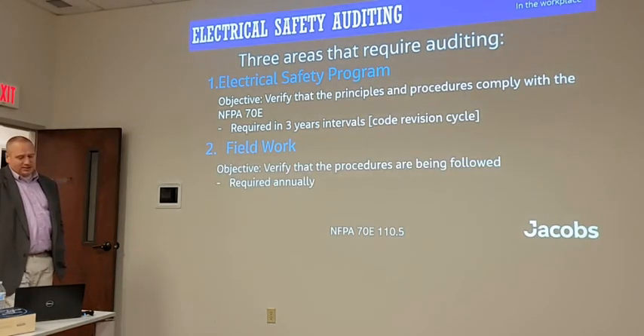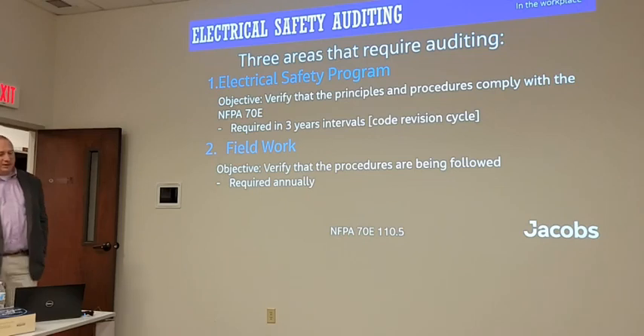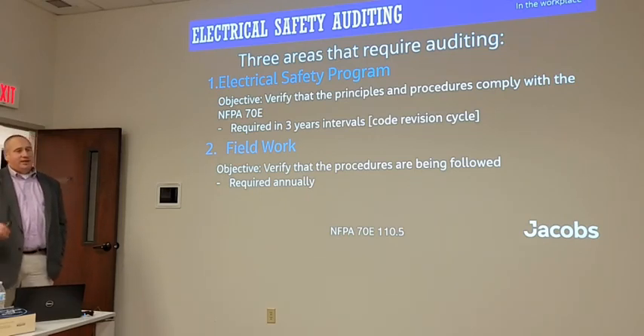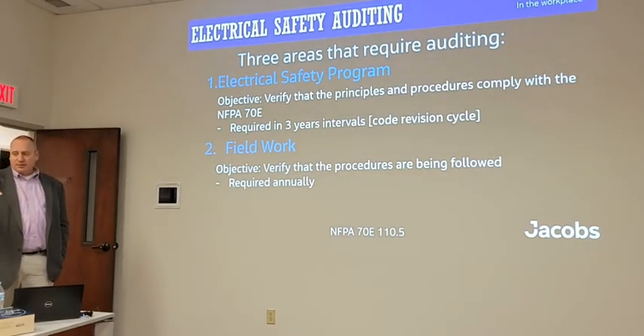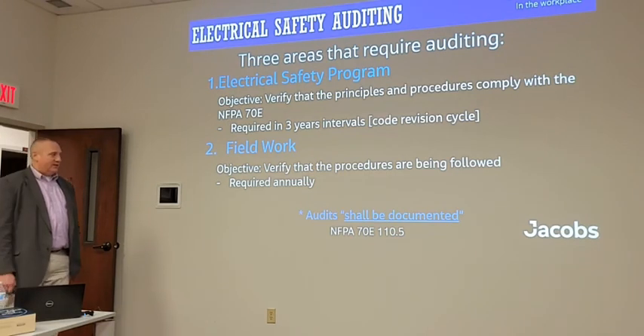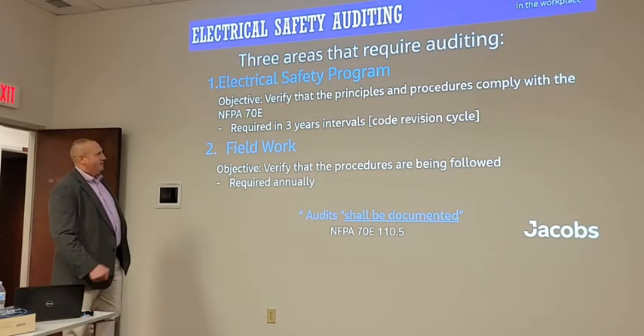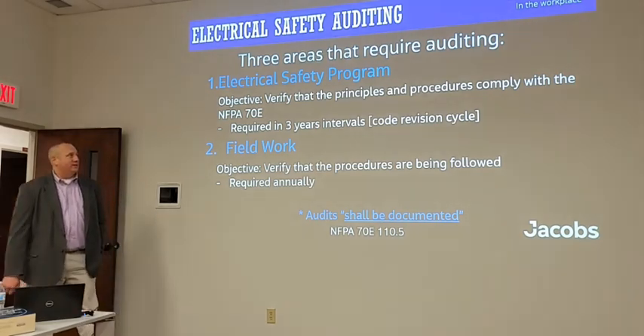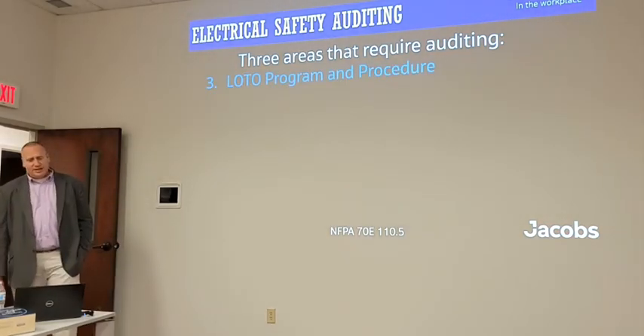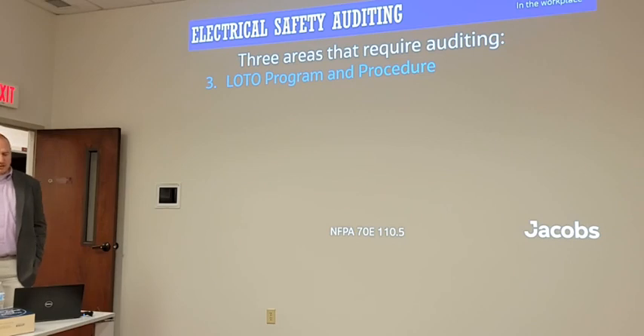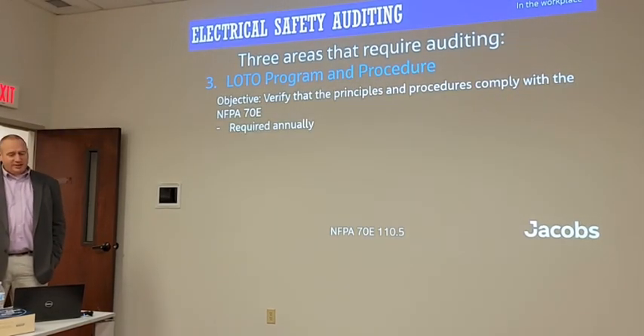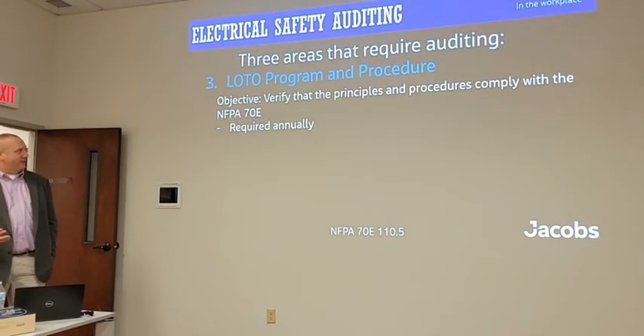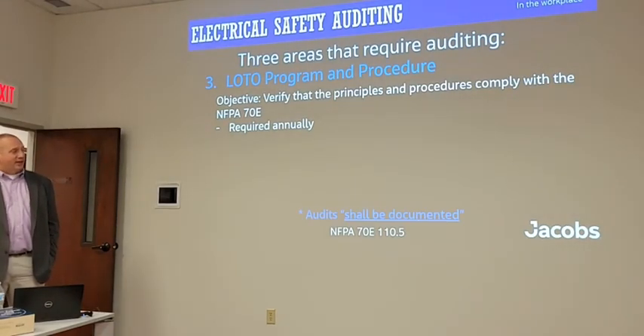And then field work audits, that's to verify the procedures are being followed. It's not just that we've got everything documented, but it's more than just putting a check in the box. Are the employees actually following the expectations of the 70E? And all the audits shall be documented. The field work has to be audited annually. And then the third one is your lockout tagout program and procedure. This is to verify that it's being followed and is compliant with the 70E, and it is required to be audited annually and documented as well.